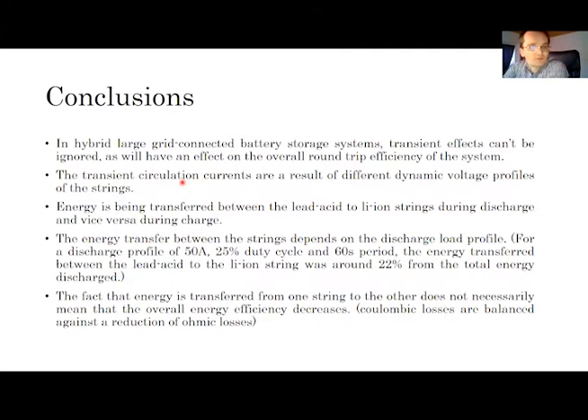And the last point, which is quite interesting: it's not necessarily obvious that this kind of energy transfer between lead acid and lithium-ion, and vice versa, is going to decrease energy efficiency. Why? Yes, you lose some charge because of the Coulombic efficiency - it's not good to charge and discharge lead acid batteries because you lose energy. But at the same time, if you get some energy from the lead acid string into the lithium-ion and then discharge into the load, because the lithium-ion battery has lower resistance than lead acid, yes you lose some charge to Coulombic efficiency, but you have lower ohmic losses. Basically it's the same effect as having a supercapacitor connected in parallel with the battery.